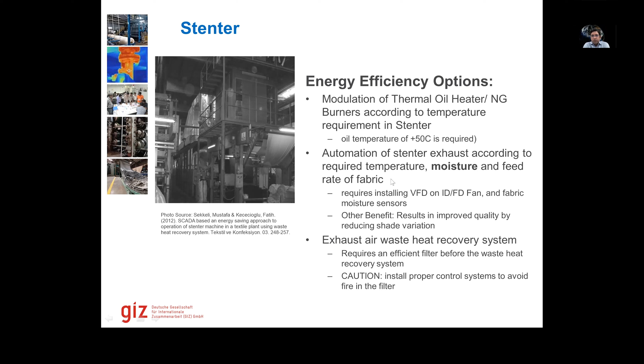So this is an actual case. The exhaust air flow we could not measure because there was no area of measurement. But in this case, we did some estimation based on the size of the stenter, the size of exhaust fans, and the amount of vanes or ducts opened. So we did some estimation here. We knew the exhaust temperature of the stenter was 160 degrees Celsius. We wanted to bring it down to 100 degrees Celsius. So delta T was 60.